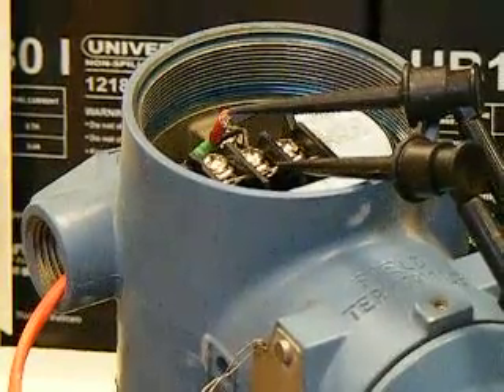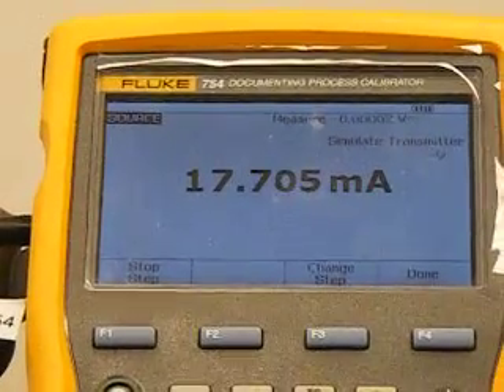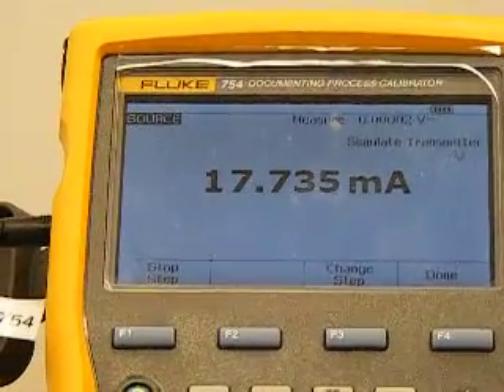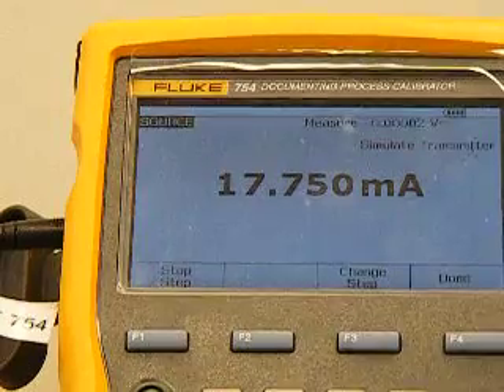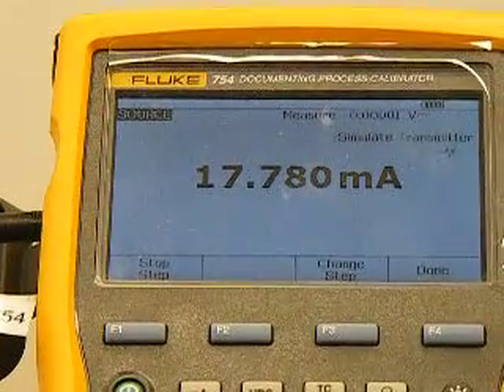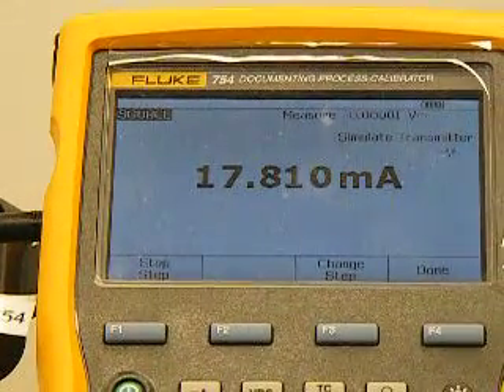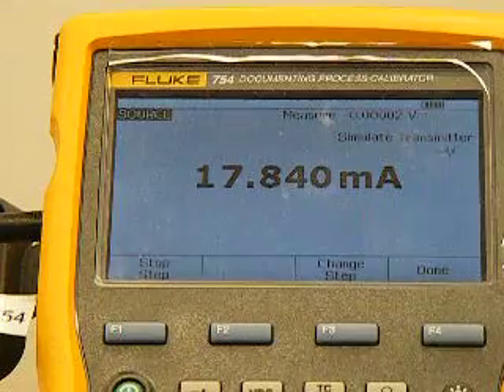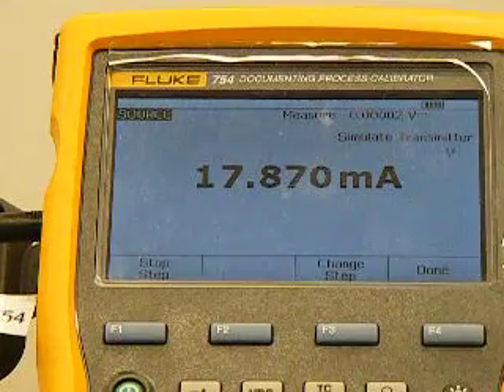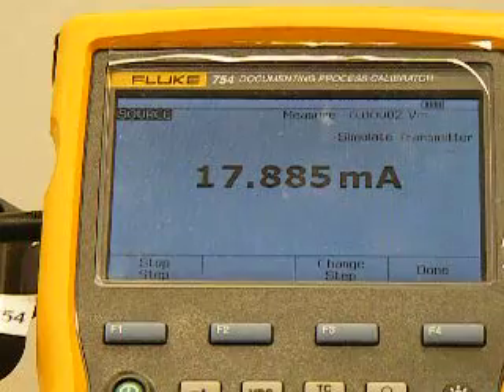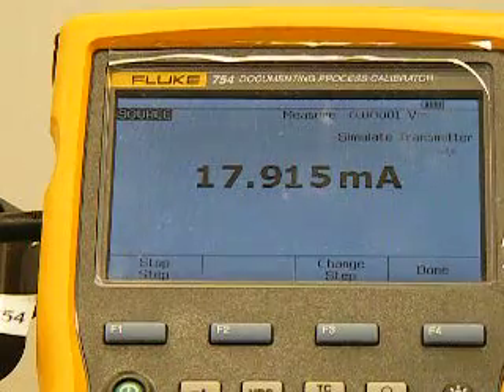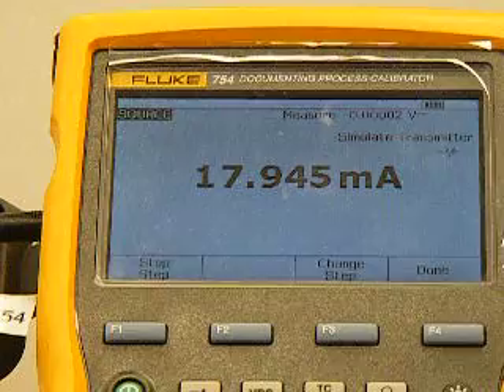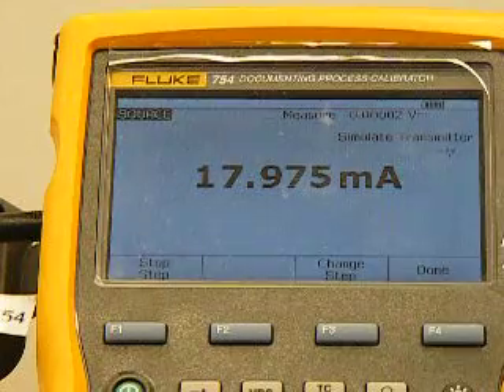Here's the industrial pressure transmitter. Right now it's in override mode. The test leads that you see there actually connect up to this piece of calibration equipment that's simulating the signal in. What happens with this, as the signal goes up and down, this is simulating your input at roughly 233 psi at mid-range.